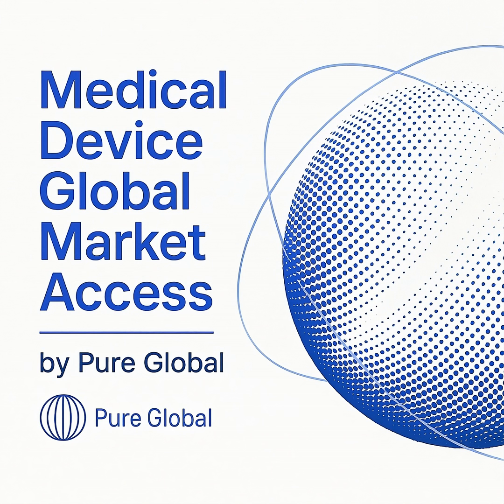Furthermore, any company that imports or sells a medical device in Canada must hold a Medical Device Establishment License, or MDEL. This is separate from the device-specific MDL. The MDEL applies to the establishment, the manufacturer, importer, or distributor, and ensures they have quality control and procedural systems in place for handling and distributing devices in Canada.